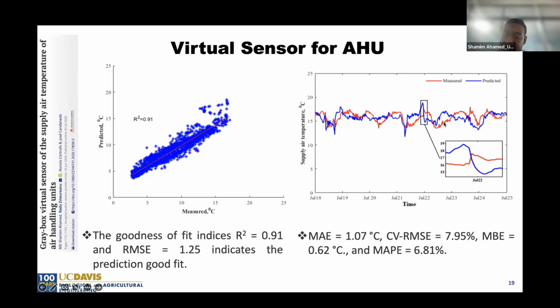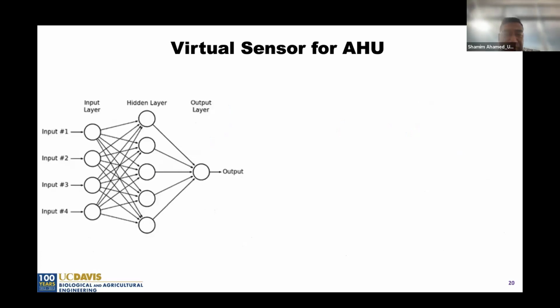As you can see, the accuracy is quite good. From that perspective, this virtual sensor algorithm could be integrated into the control system to do some self-calibration of the sensor, and in some cases it could be a complete replacement of the physical sensor.